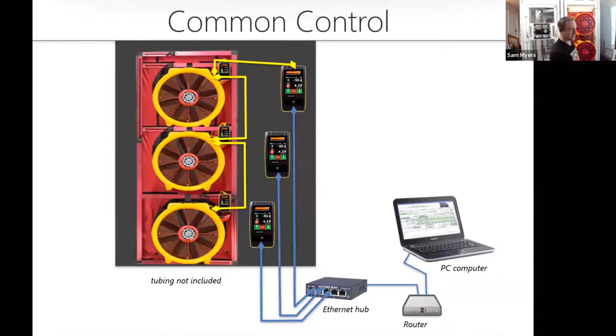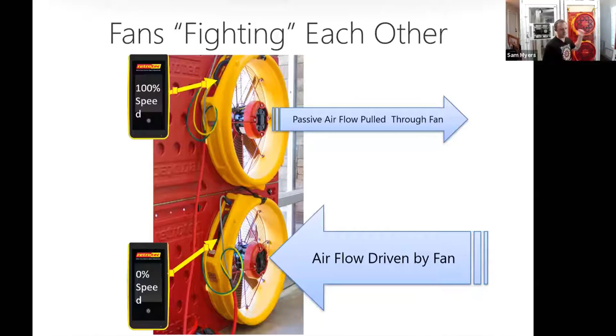Yeah, and so with the individual control, we've seen it in some cases where one fan might get pulled into the backwards direction by another. So having the common control where everything is tied in and running at the same rate at the same time, you're never going to have that problem. And you can always just have them open and start off at the same time.